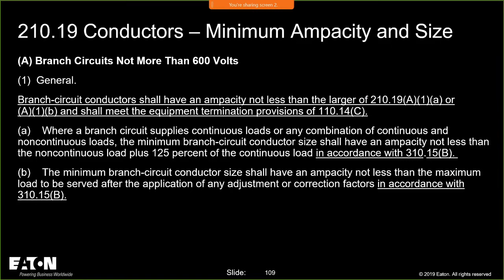Now, we didn't change the intent here, but what we did was we made it read right. It never read correctly. And this was a part of my ampacity task group that I chaired. When we read through this, we said we didn't want to change the intent, but we did have to make it read better, so that we make it aware that when you do the branch circuit conductors, they have to have an ampacity not less than the larger of the two conductors that you determine. So you determine the conductor size based upon the continuous loads and the 125%, but not working in the conditions of use and the correction factors. You just do the 125% based upon the continuous loads, and you do that in accordance with 310.15(B).